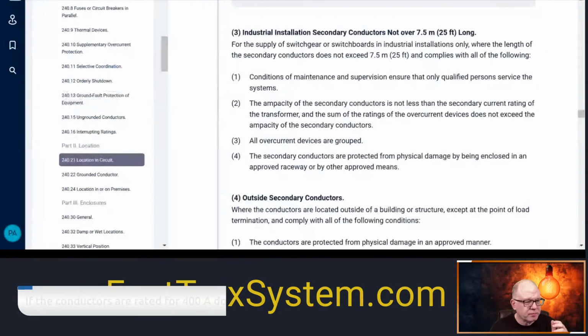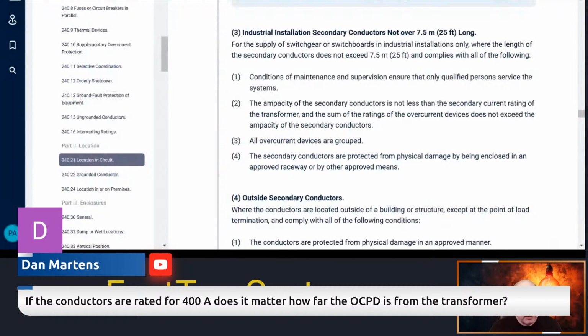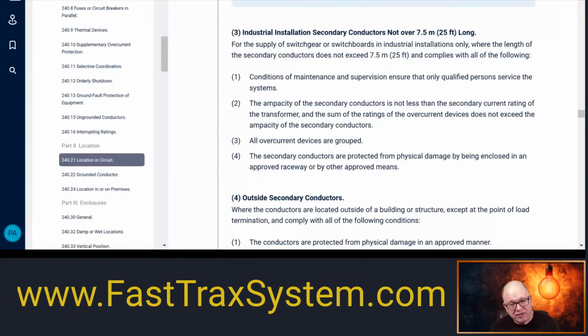We got a question. And Dan asks, if the conductor is rated for 400 amps, does it matter how far the overcurrent protector is from the transformer? Yeah, so if you're utilizing the 10-foot rule, then yes, it matters. You know why it matters? Because there's no overcurrent protection at the connection to the transformer. So this is a limiting length rule because there's no protection there. And so you're utilizing this secondary conductor rule because there is no protection at the point where it makes a connection to the transformer. Now, if you want to put a 400 amp right there at the transformer, then after that, it doesn't matter how far you go because those conductors are protected. But the whole premise of the rule here is you're applying the 10-foot rule.